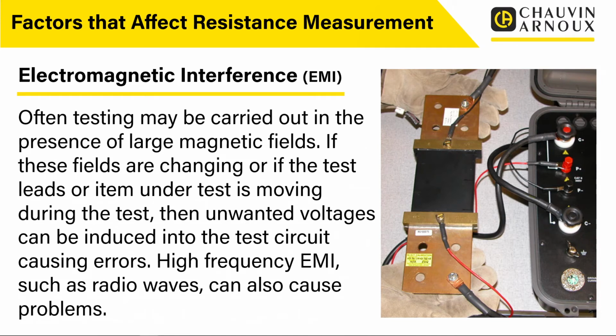High frequency electromagnetic interference, such as radio waves, can also cause problems. So we've got what we might call low frequency, the general mains frequencies, generating these electromagnetic fields. We've got electromagnetic fields induced by us moving the test piece or moving the test leads within a magnetic field. But then we've also got these high frequencies that are all over the place. This could be Wi-Fi, a TV signal, a radio signal, another transmitter, or anything like that that's present. All of these things can induce voltages into the test circuit, and again can cause problems.